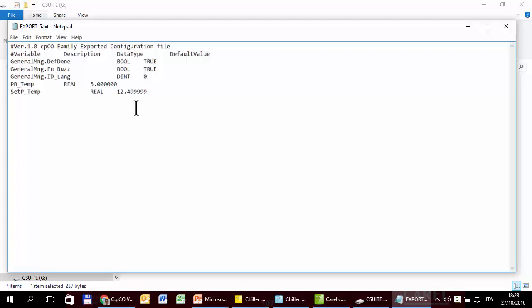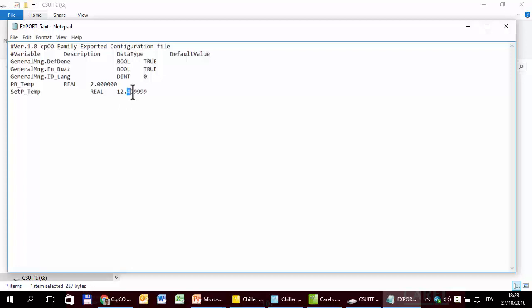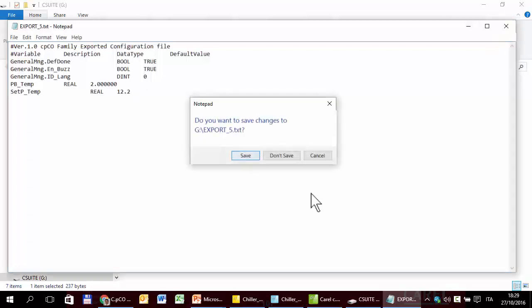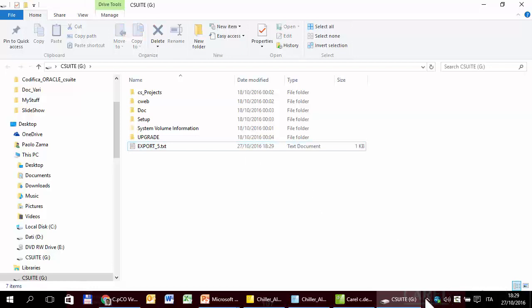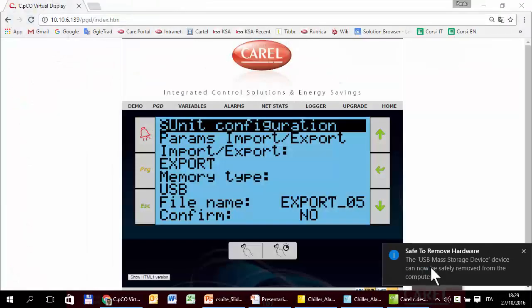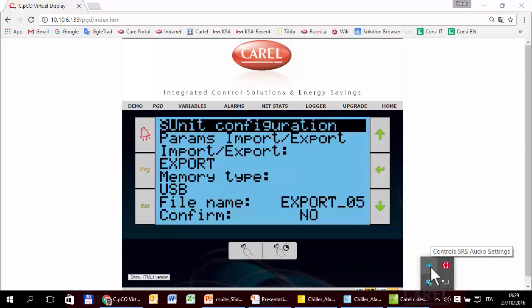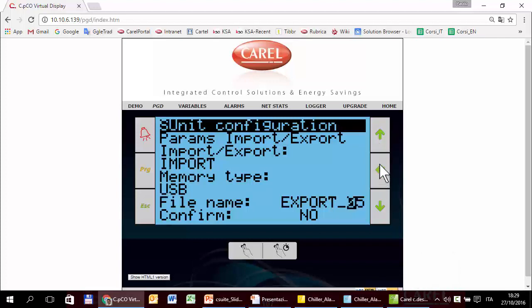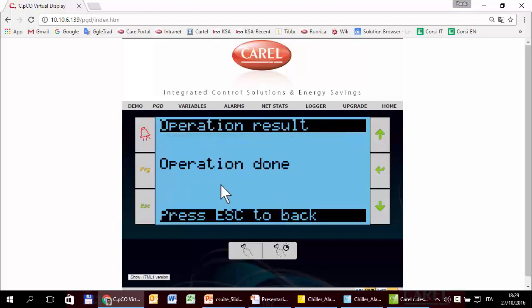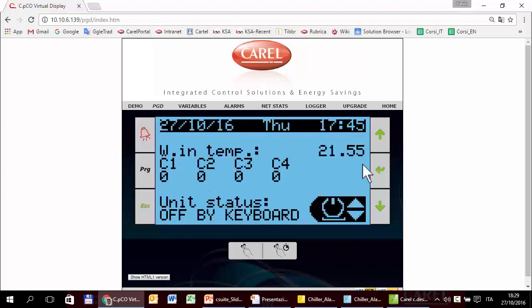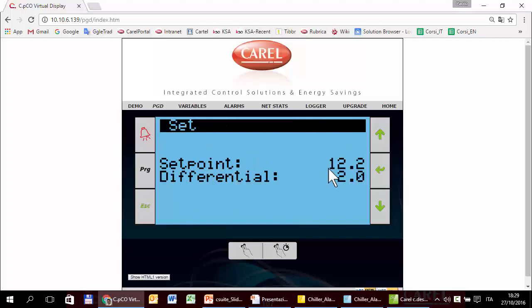Now we try the opposite: import the configuration. We change the proportional band to 2 and the setpoint to 12.2 — easy to remember, 2 and 2 — and save back to disk. We plug the pendrive back in and this time do import with the same file number. Operation done. The setpoint is now 12.2 and the proportional band is 2.0, as expected.